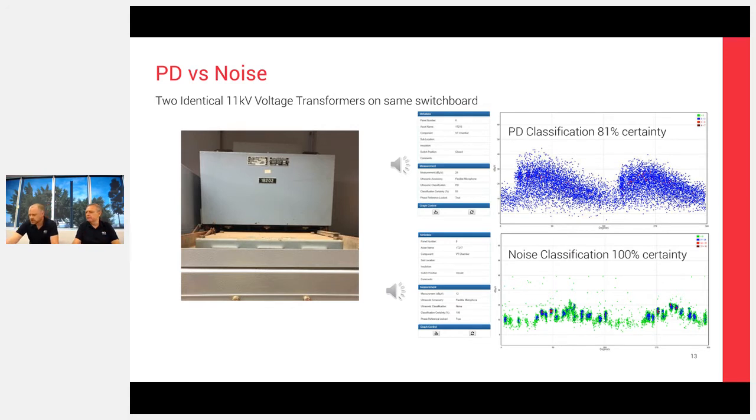Just got one question here, Neil, from James Fry. What would the VT PRPD pattern look like if it weren't phase locked? If you didn't achieve a phase lock using the instrument on the opto sensor to lights, then what you could actually do in both of these instances is manually adjust the phase lock so that you still achieve these two patterns.